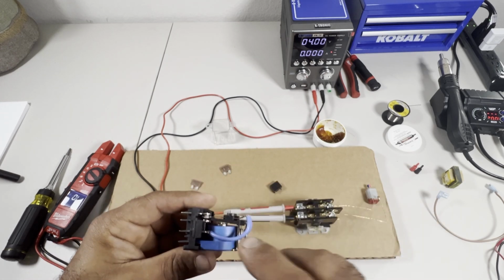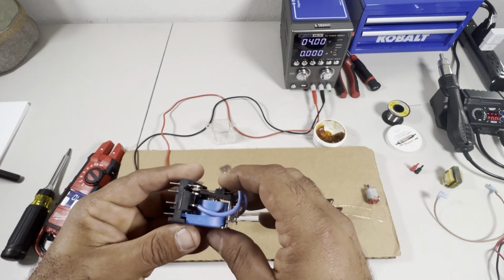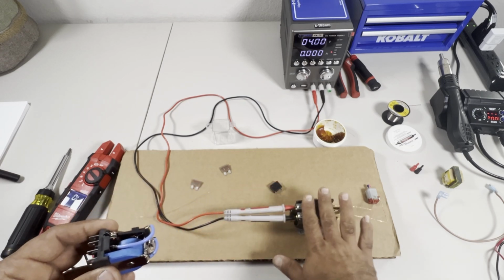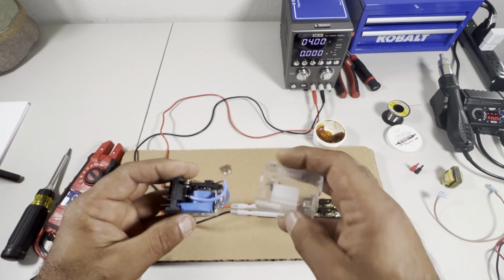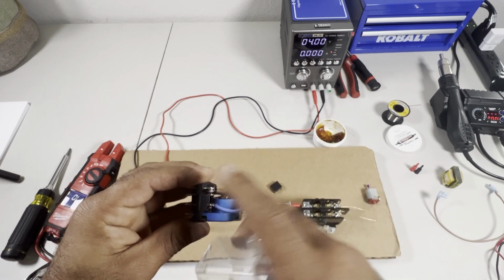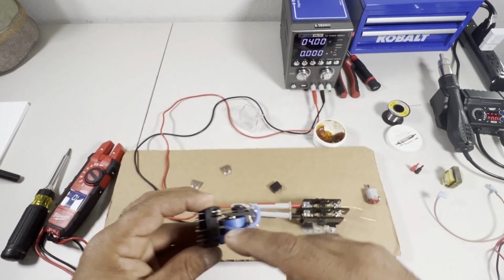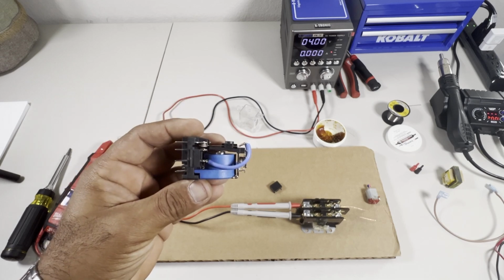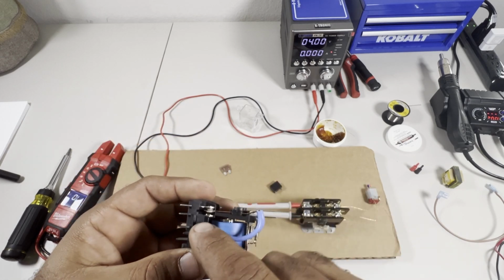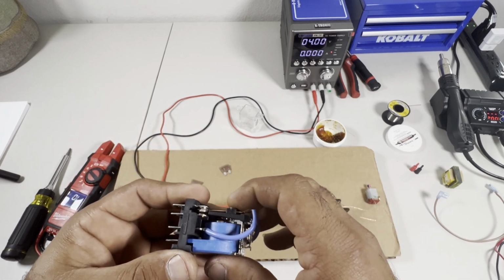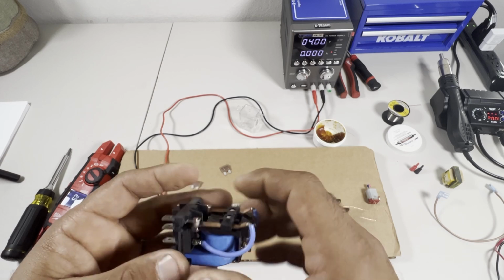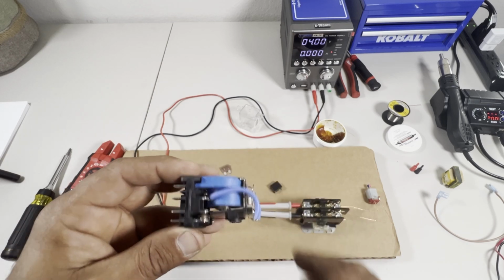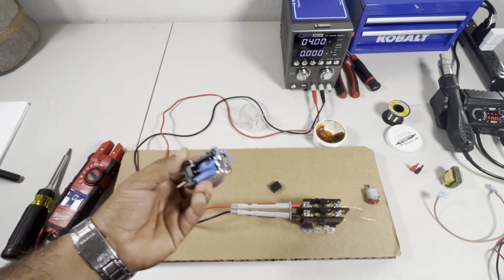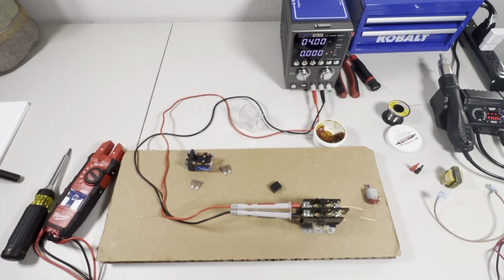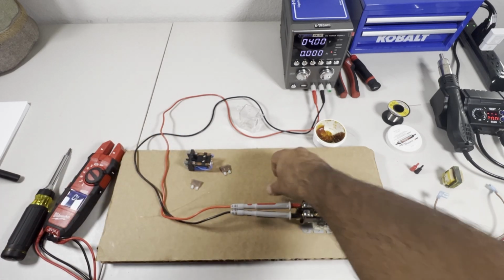So what you always want to check for in any relay that is visible, sometimes they have a dust cover on it. That's pretty much what it is, a dust cover. Because when dust gets inside the contacts, it's going to cause resistance. You want to check to see if those contact points are clean or if they're burned, blacked out, or whatever the case is. And if you see that they have a sign of arcing, that relay is gone.